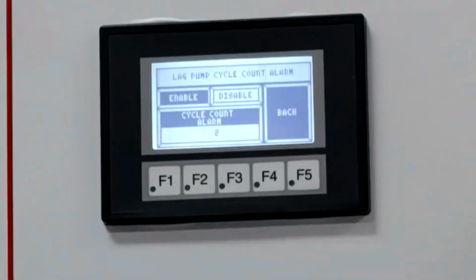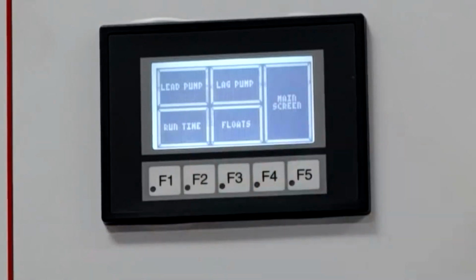And really what I'd like to show you is that lag pump counter. That was something that we added to address having a 4-float system and being able to get that feedback that you have a lag pump coming on, so that you get some alarms before both of your pumps fail. Really not a good situation for storm or sanitary. So you can adjust how many times that lag pump has to come on before you get the alarm. It's a cumulative count, but that way you get early indication that you might have an issue with your pit rather than waiting for both pumps to fail.